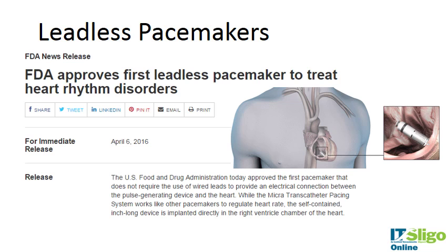An FDA press release from April this year states that the Food and Drug Administration approved the first pacemaker that does not require the use of wired leads. It's called a Micra Transcatheter Pacing System. It works like other pacemakers to regulate heart rate. The self-contained, inch-long device is implanted directly into the right ventricle chamber of the heart — not much bigger than a vitamin pill.